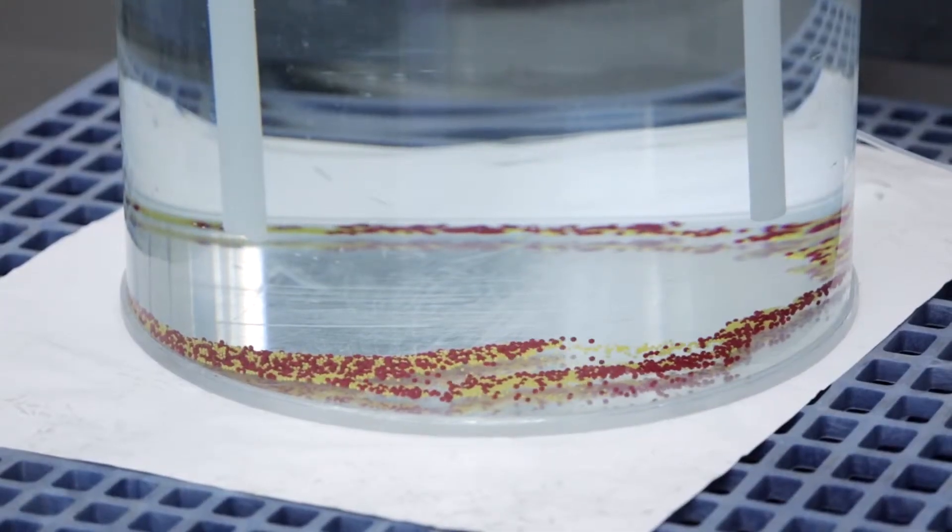For slurries with heavy settling, pump recirculation is not recommended. We have a way to look at it so we can see that it is effective in re-homogenizing stratified slurries which don't have heavy settling, and I'll show you that next.